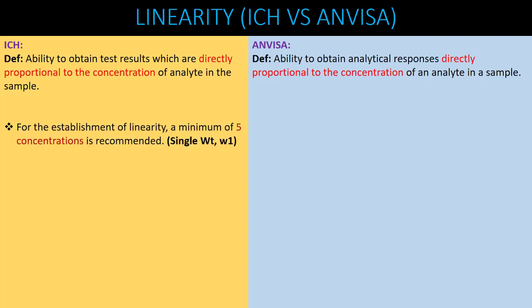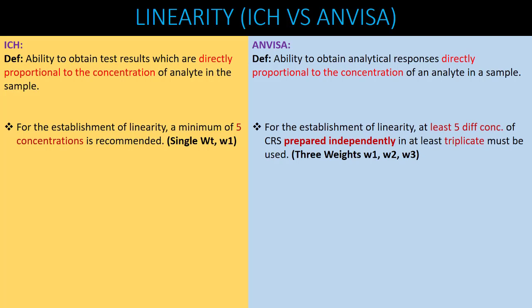Regarding requirements: ICH recommends a minimum of five concentrations, prepared by making a single stock solution and further diluting it to the required concentration levels. ANVISA, however, requires at least five different concentrations of CRS (certified reference standard) prepared independently in at least triplicate. You need to weigh the reference standard in three different weights independently, make stock solutions, and from these three independent stock solutions prepare five different concentration levels.